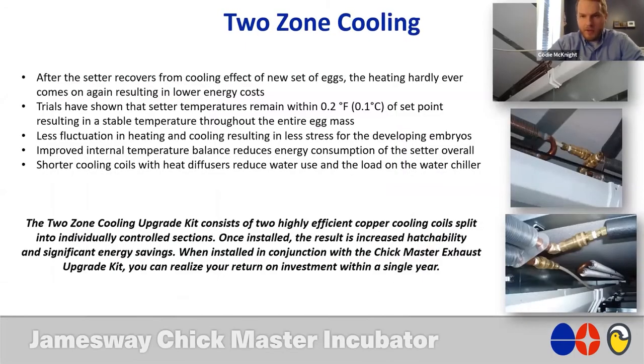On to our two-zone or split cooling. Split cooling is the alternative to those traditional cooling coils that were installed in the machines before we developed split cooling. You have turned your machine, when you get this upgrade, into a zonal cooling capable machine. You can manage the front of the machine and the back of the machine independently. That's going to lead to more stability in your incubation cabinet, greater control over your incubation cabinet. The studies have shown we can remain within 0.2 degrees Fahrenheit of set point with this upgrade. That is huge. For you to have a stable environment for your developing embryos is invaluable.